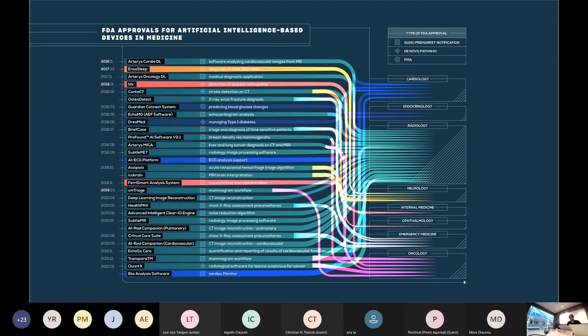But now they have actually established fairly good guidelines, and there's a proper way of assessing them and getting through the regulatory system. So the whole approval process is now fully functional. And the processes of approval are both de novo and 510(k). There's a very good review of this whole system, if ever it's of interest, in Nature that was just published, as I said earlier, this fall.